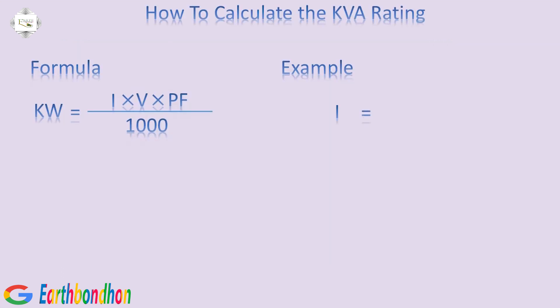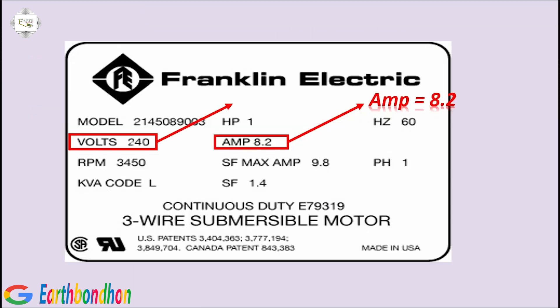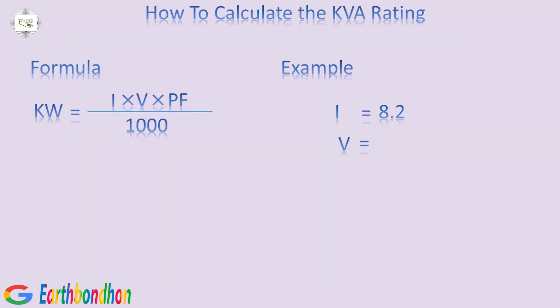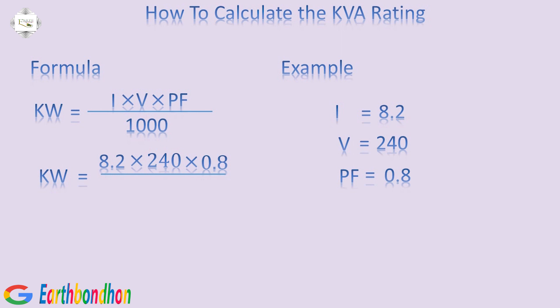Current equals 8.2 Amperes. Volts equals 240. Power Factor equals 0.8. Kilowatts equals 8.2 Amperes multiplication 240 multiplication 0.8 division 1000. Kilowatts equals 1.5 Kilowatts.